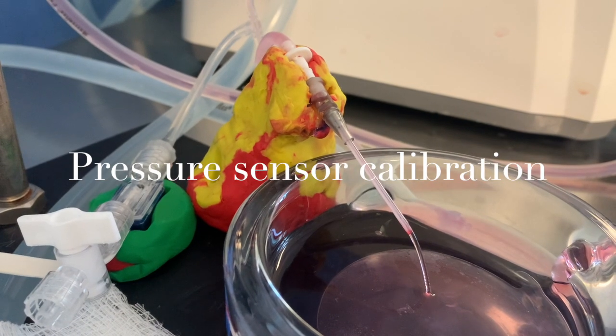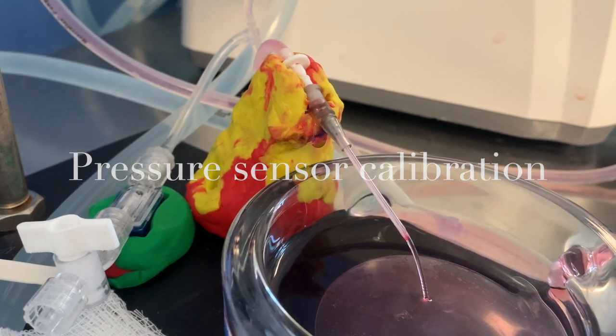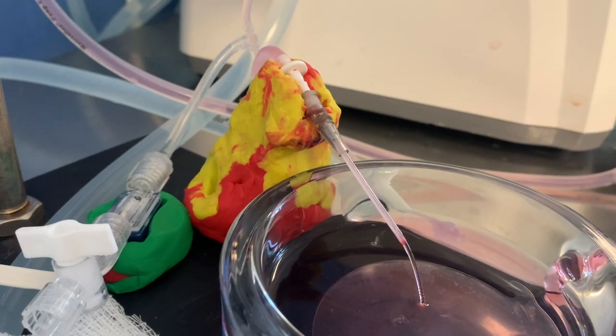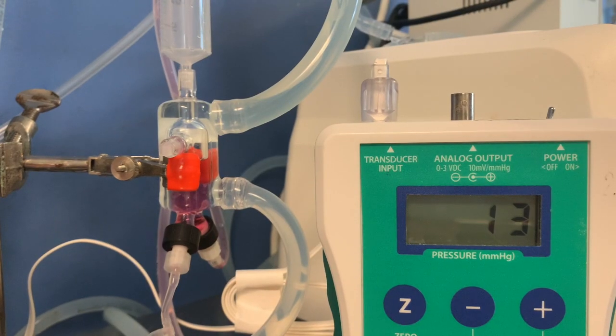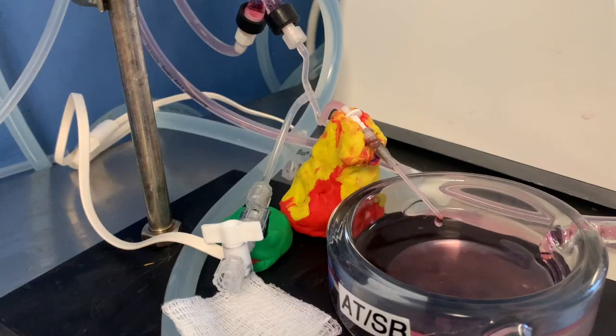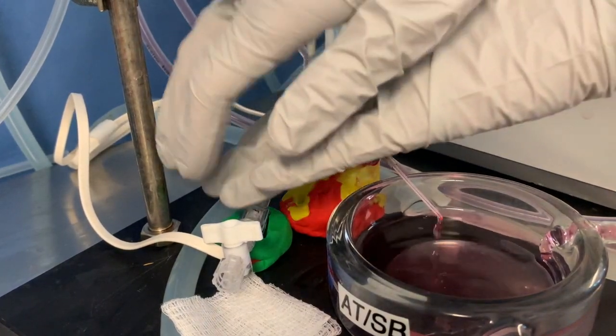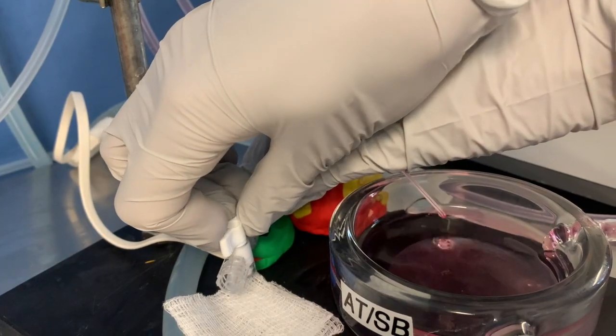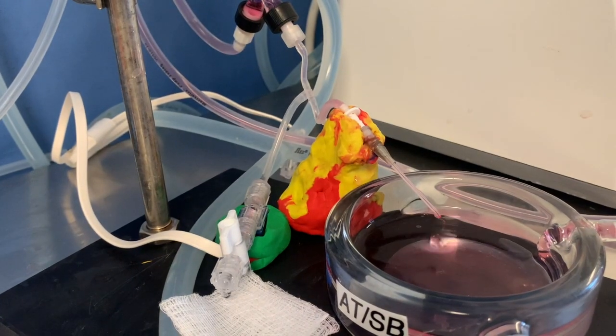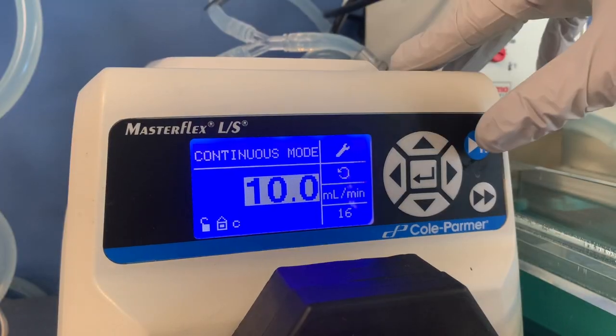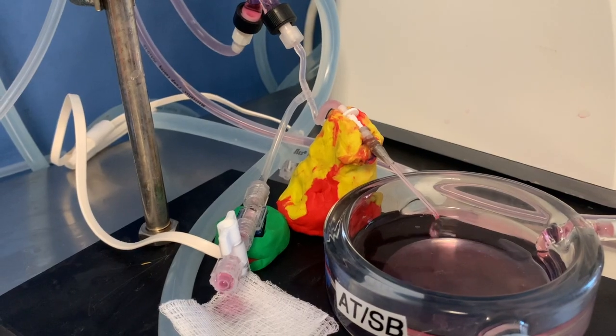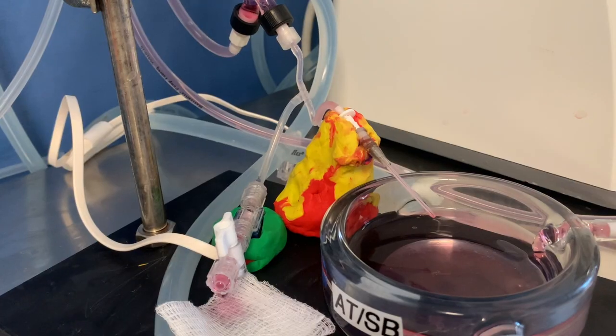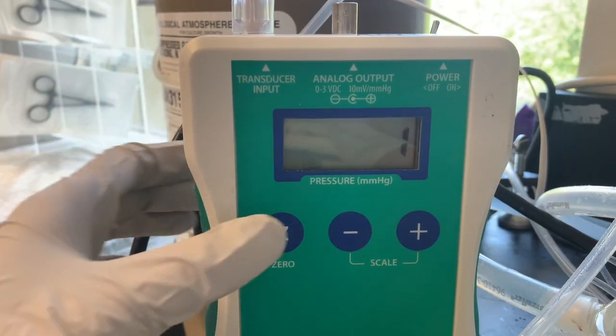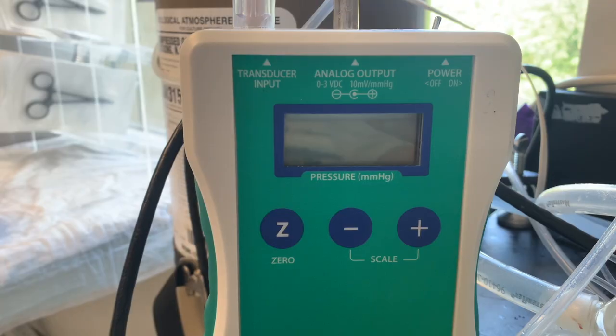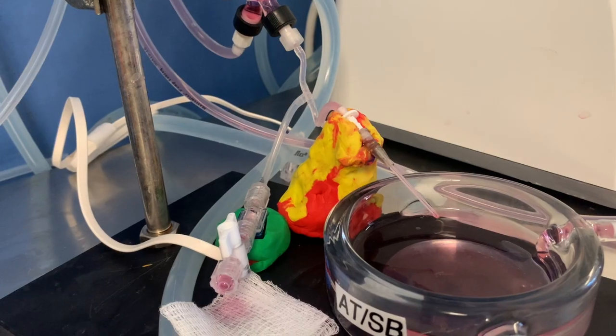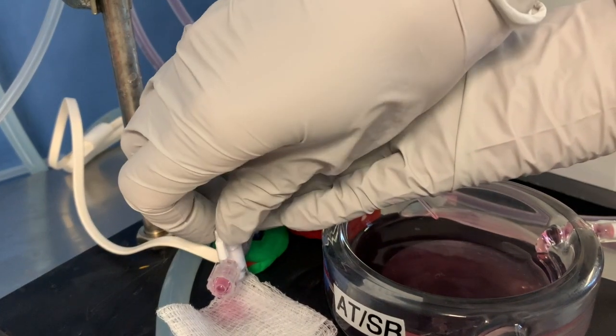To accurately measure pressure in the organ, the pressure sensor must be placed at the same height of the organ. First, we must calibrate or zero the pressure monitor. To do this, the gauge will be opened and the sensor will fill with perfusate. The flow is paused until the dripping stops and the movement of fluid comes to a standstill. We press the zero or calibration button and the gauge is closed. From this moment on, it is important not to move the position of the sensor and cannula in order to secure accurate readings.